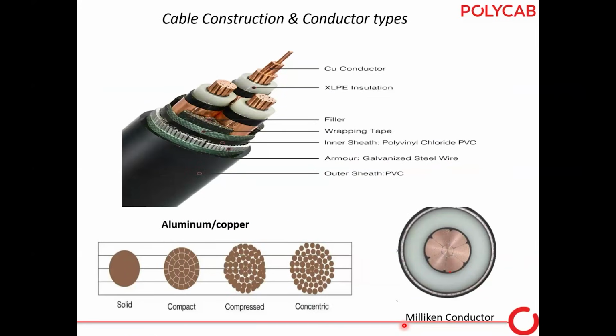Let's understand the construction of the cable. As I understand, might be all of you are from the same field, so you know the cable construction very well. But I will just run through this in a few seconds. This is a 3-core copper cable. Copper conductor is there. Over that, if you see, a semi-conducting layer is there. Over that XLPE insulation. Over that again a semi-conducting layer. These three cores are bound together, and to give the round shape we use fillers. Over that a wrapping tape is always there. Over the wrapping tape, armoring is there. And over the armoring, the outer sheath is there.